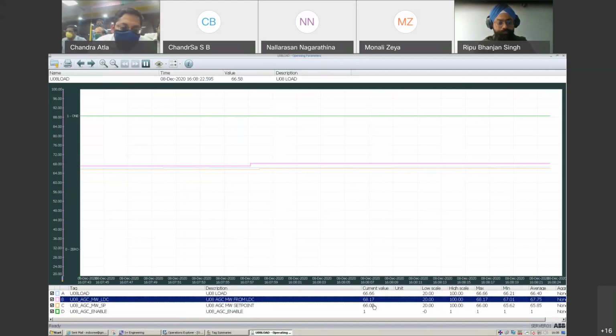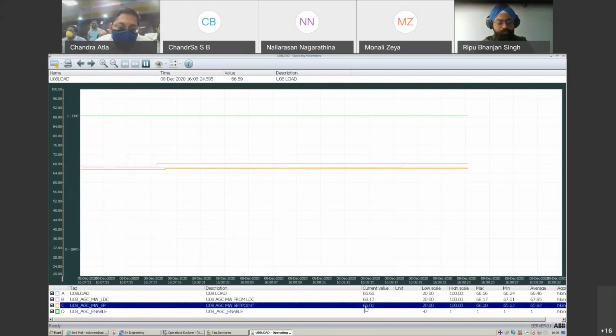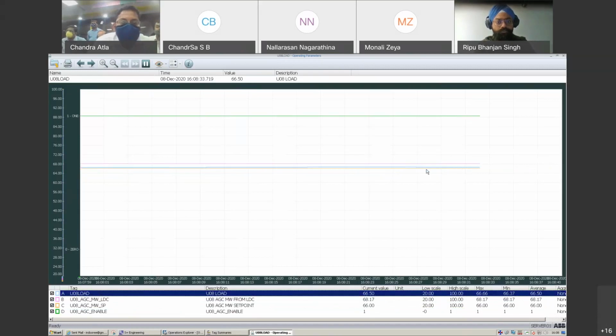However, the limit we have mentioned is plus or minus 10% of the set point scheduled, so that is 66 only. The actual generation of the unit will not cross 66, and it will stop there because that is my boundary where I can support the grid. So that 10% is completed.